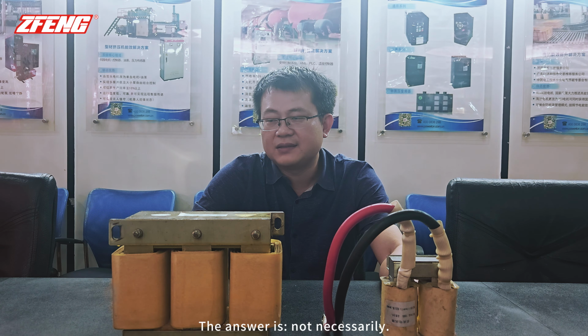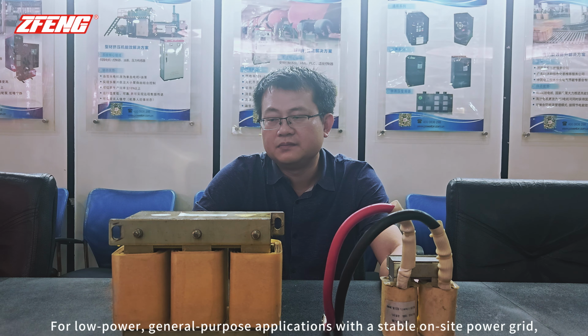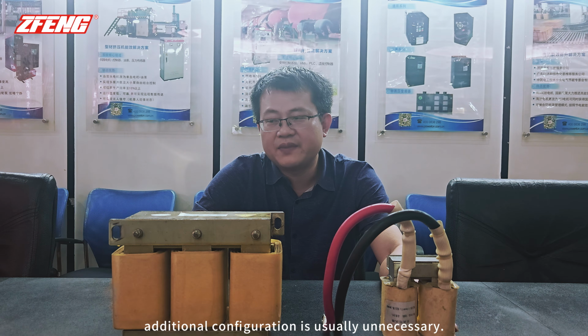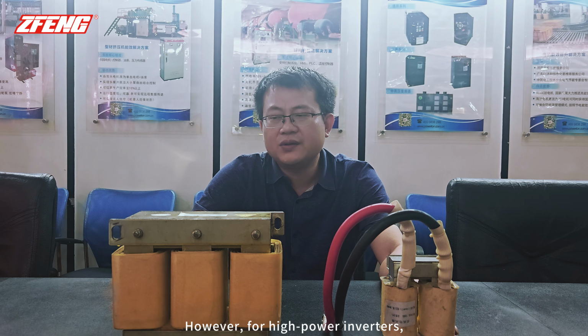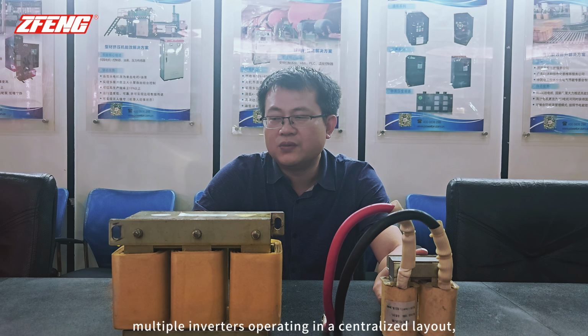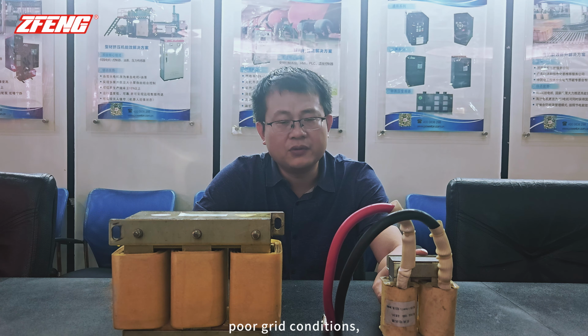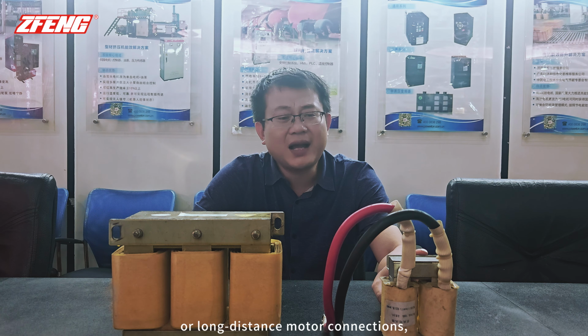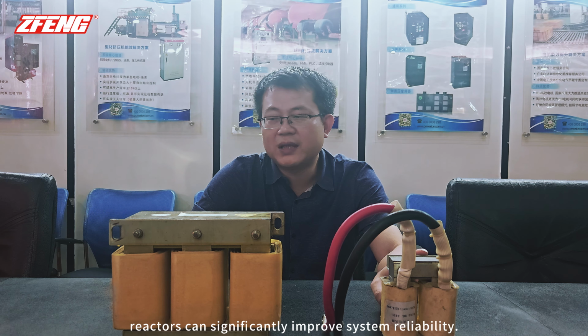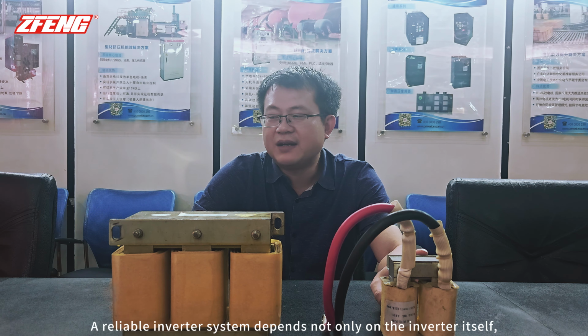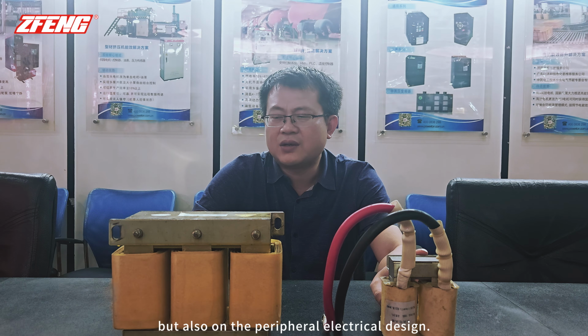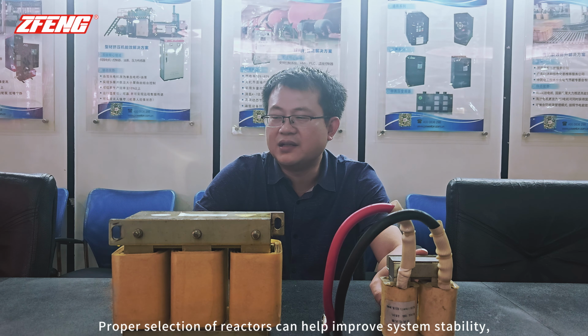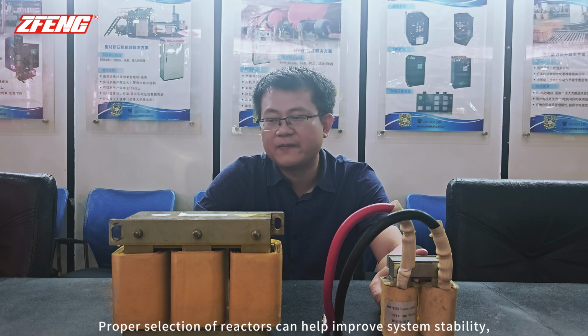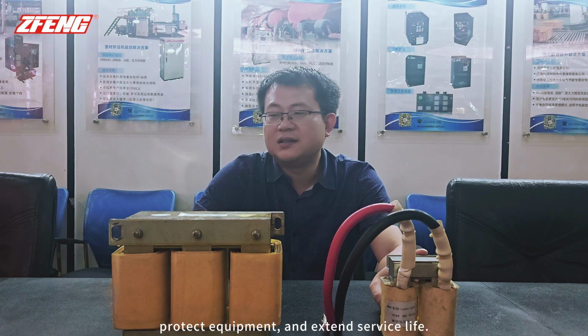The answer is not necessarily. For low-power, general-purpose applications with a stable power grid, additional configuration is usually unnecessary. However, for high-power inverters, multiple units operating in a centralized layout, poor grid conditions, or long-distance motor connections, reactors can significantly improve system reliability. A reliable inverter system depends not only on the inverter itself, but also on proper electrical design. Proper selection of reactors can help improve system stability, protect equipment, and extend service life.